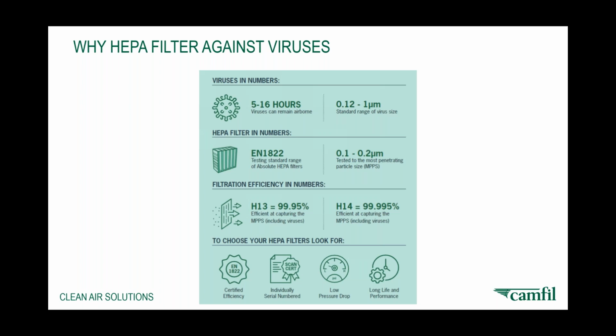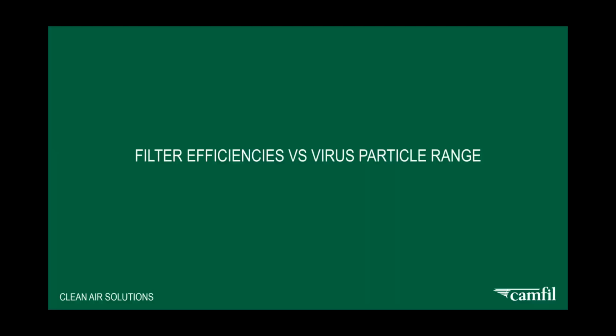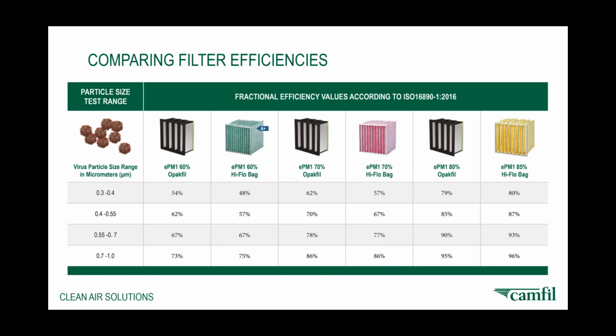And let's look at those filter efficiencies versus the virus particle ranges. So we look at virus particle range in micrometers, microns there on the left-hand side, between 0.3 and 0.4 microns, between 0.4 and 0.55. And again, bear in mind, viruses can be smaller, but they tend to travel on larger particles in the air. They're not just floating around on their own. They'll attach to larger particles. So we can take particle sizes of 0.3 to 0.4 microns, right up to 0.7 to 1 microns on the bottom. And you can see the increasing efficiency as we increase in filter efficiency.